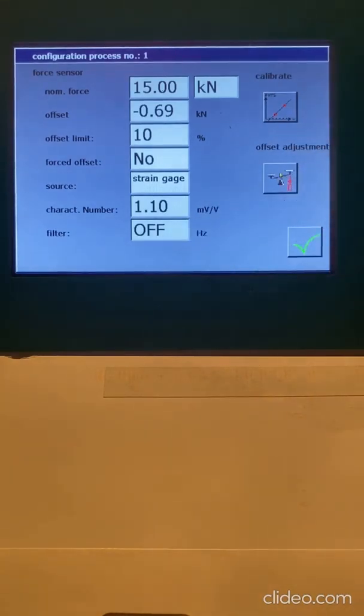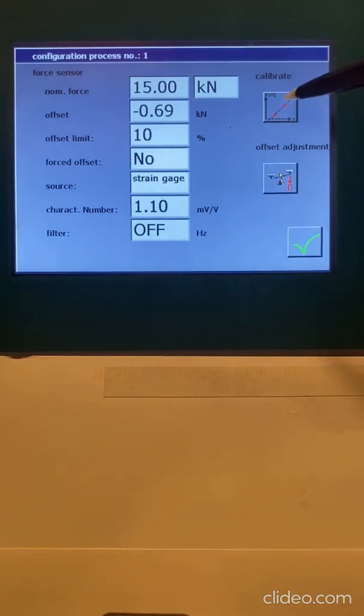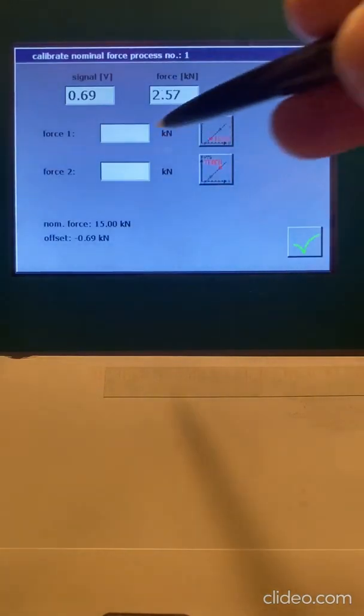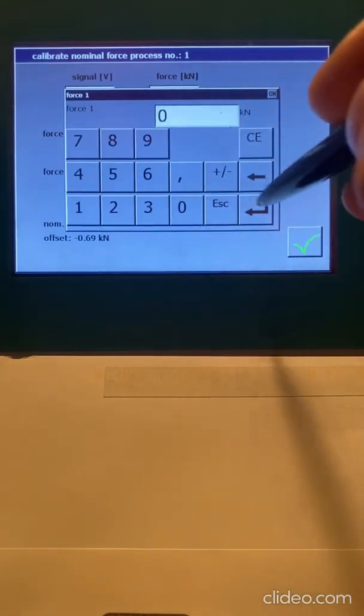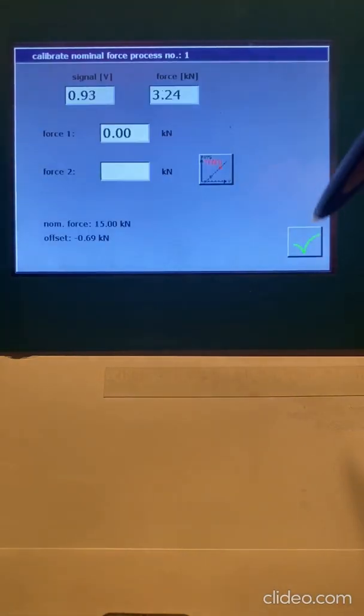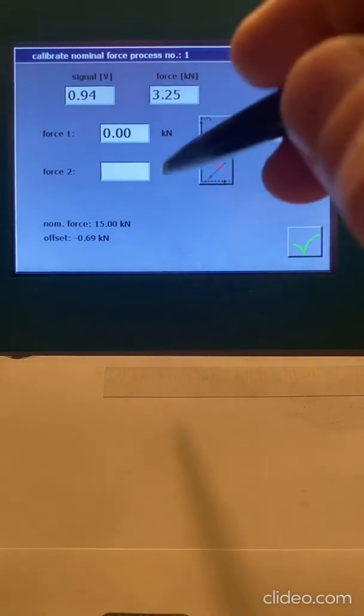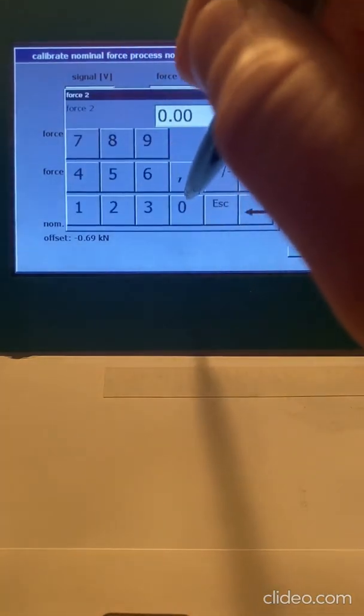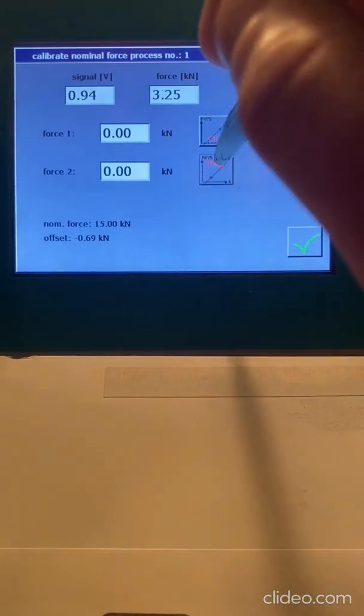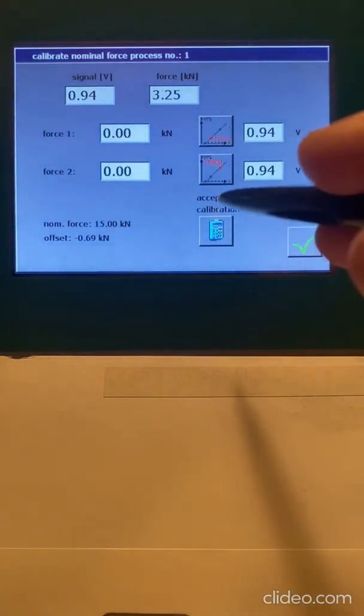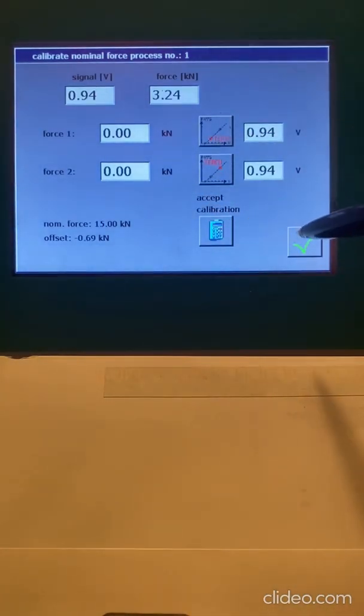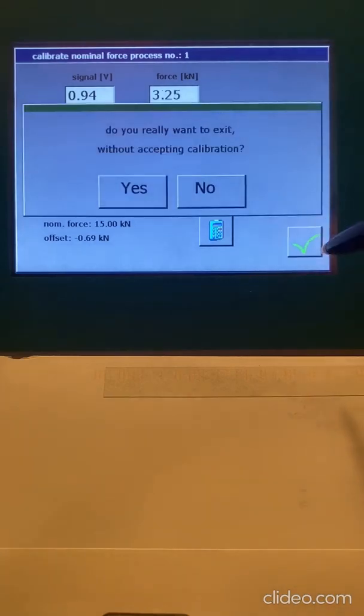So when I'm setting this up, typically we want to do either a two-point calibration, and you hit this button here, and you're going to get a two-point calibration. Let's see, I type in zero, and then I hit teach. It just grabbed, 0.94 volts is zero. And then I can type in zero again, and hit teach, and then I can accept the calibration. So this is a way that you would go ahead and do a two-point calibration. Yes.